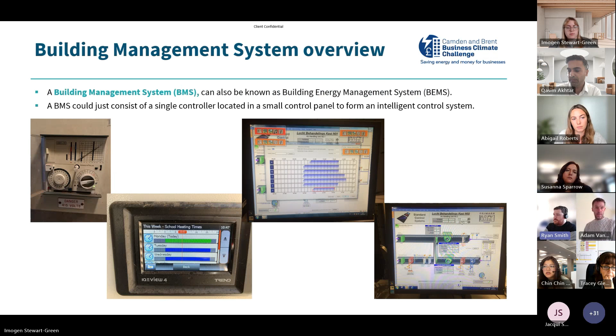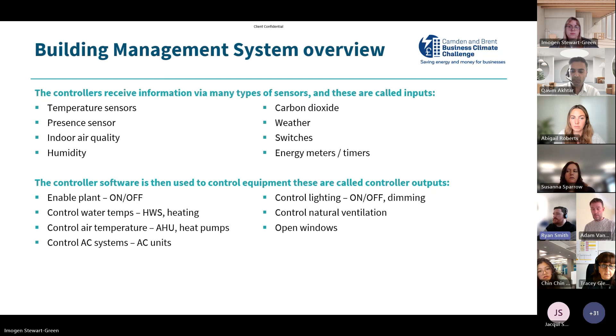So the controllers receive information via many different sensors. That could be temperature, presence sensors, like Imogen was talking about with the lighting, air quality, humidity, carbon dioxide, and that then feeds into the BMS, and that can control a range of different outputs. That could enable plant on and off. It could change the control water temperatures for the hot water or heating, air temperature for the same, could open windows, control lighting and so on. It varies depending on the setup of your BMS. Next slide.